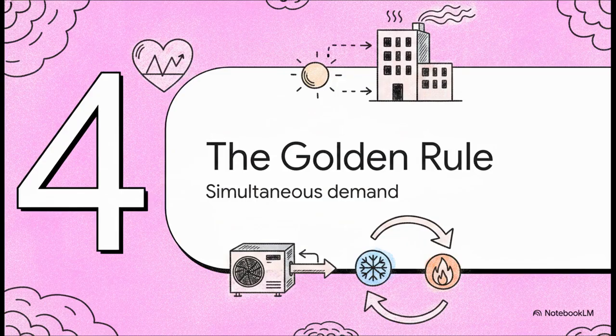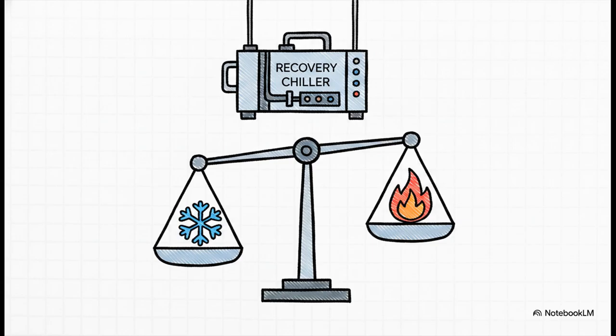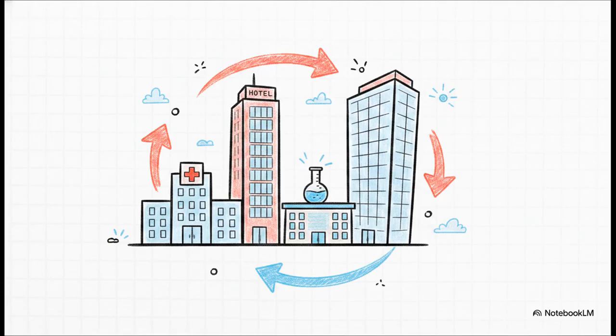Moving on to Section 4, the Golden Rule of Recovery. Now, there is a catch. The golden rule of this technology is super simple, but it is entirely uncompromising. A heat recovery chiller works best when there is a cooling load and a heating load at the exact same time. Without those simultaneous loads, the whole concept basically falls apart. If your building only needs cooling, the machine literally has nowhere to put the captured heat. If your building only needs heating, well, the machine doesn't have a source of heat to recover in the first place. Because of this strict rule, certain facilities are absolutely perfect candidates.